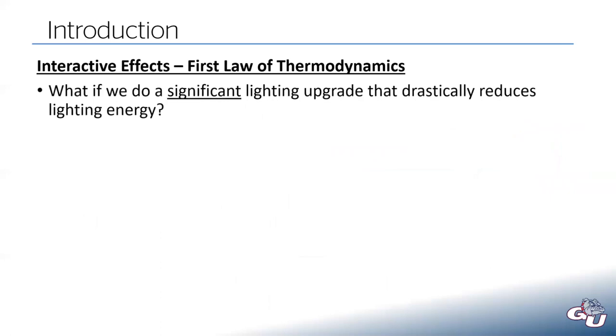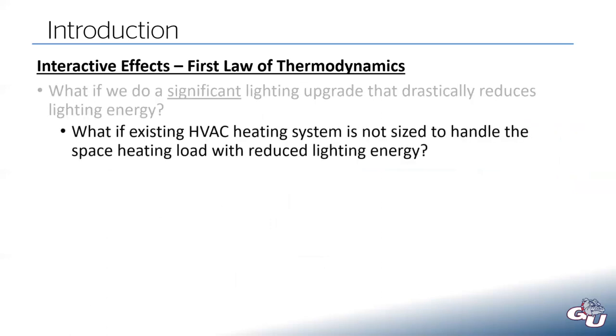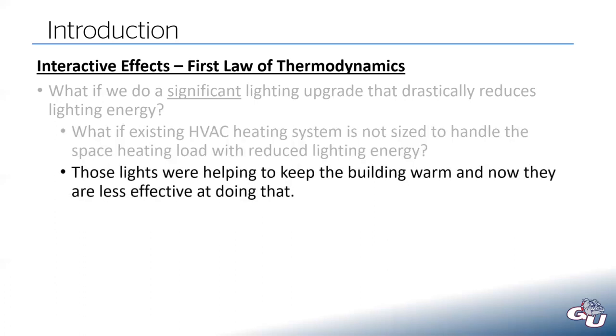And what if we did a significant lighting upgrade where we have a drastic reduction in that lighting power and lighting energy? But what if the HVAC heating system is not sized to handle what we call the space heating load with reduced lighting energy. And those lights that were in the room, they were helping to keep the building warm. And now, because you've replaced them all, they're less effective at keeping the space warm, and your heating system has to make up the difference. And what if that difference is so great that the heating system cannot keep up now that you've upgraded these lights?